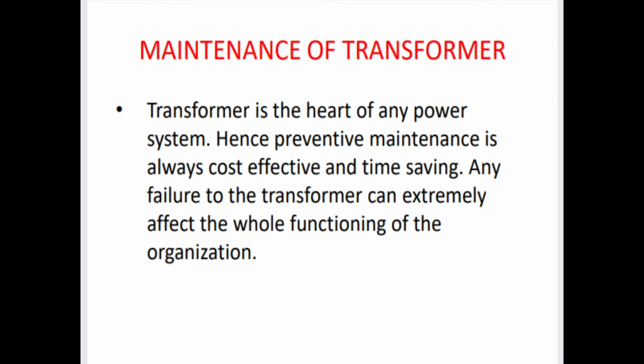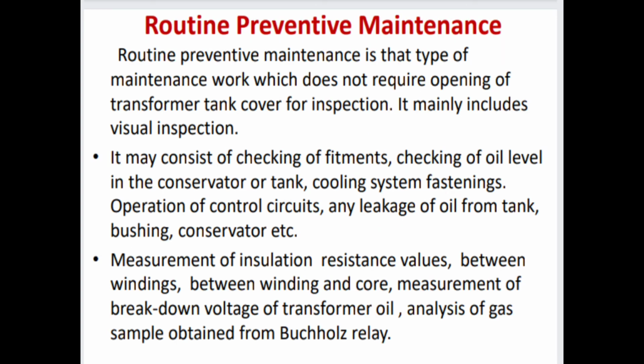When the transformer fails, then all systems fail. Then we see what routine preventive maintenance means. Routine preventive maintenance is that type of maintenance work which does not require opening of transformer tank cover for inspection. It mainly includes visual inspection, and it may consist of checking of fitments, checking of oil level in the conservator or tank, cooling system fastening, operation of control circuits, any leakage of oil from tank, bushing, conservator, etc. Measurement of insulation resistance values between winding and core, measurement of breakdown voltage of transformer oil, analysis of gas sample obtained from Buchholz relay. Means routine preventive maintenance is a type of test.